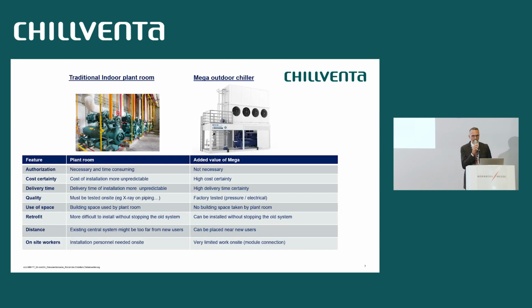If we compare a traditional plant room with this kind of chiller, there are many advantages, but let's highlight two or three of them. For example, you don't need a plant room, so you don't need to go through the process of authorization to build an ammonia plant room, and this sometimes is time-consuming and can be very complicated, especially in certain countries. And then clearly, quality, because this is a plug-and-play system which is built in a factory and can be tested there, so we can solve all the issues in the factory before the delivery to the customer, and fixing an issue in the factory is much easier and cheaper than fixing the issue on site, as we all know.